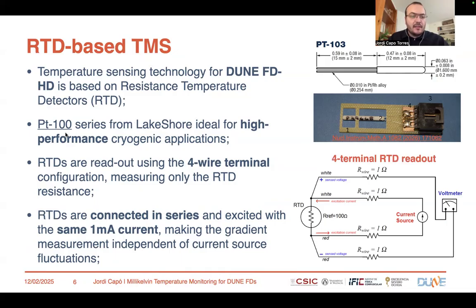What we have used are these PT100 series from Lakeshore that are ideal for high performance cryogenic applications. You can find more information about this series in this link here. They look like this in the top right image here in the slide. And we read them out using the 4-terminal configuration, ensuring that we only measure the RTD resistance as measured at the very end of the terminal of the platinum sensor. We have all of them connected in series, and we excite them with the same 1 milliampere current. In this way, we make the gradient measurements totally independent of potential current source fluctuations.